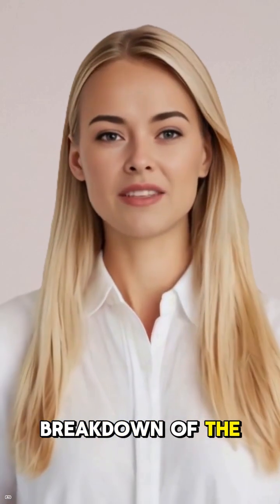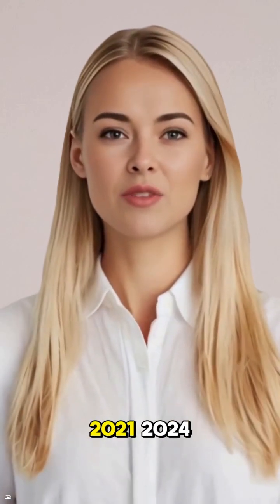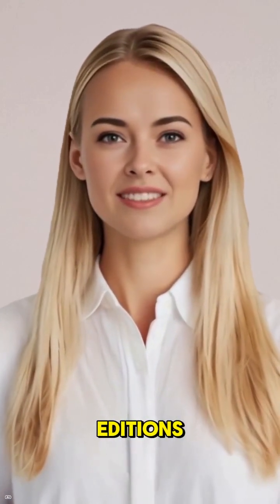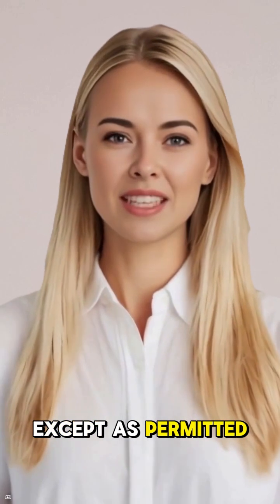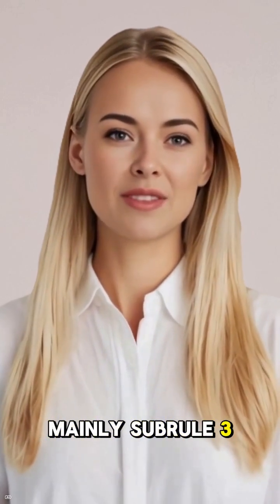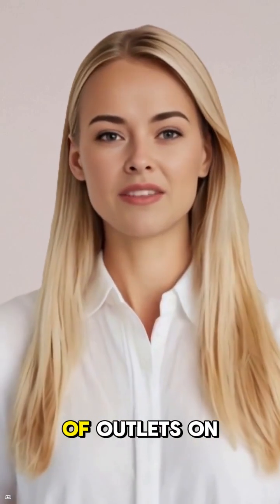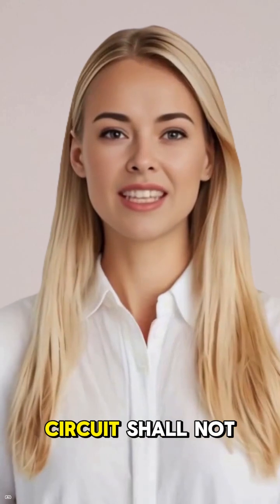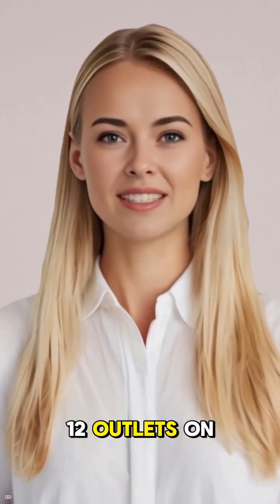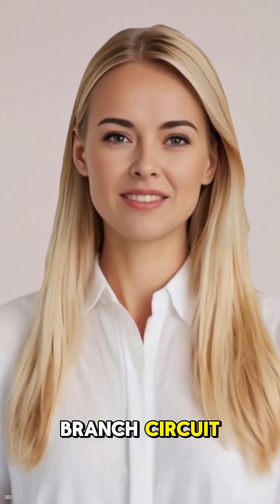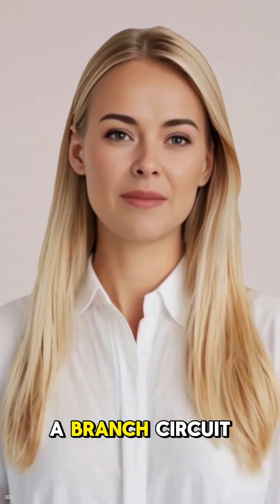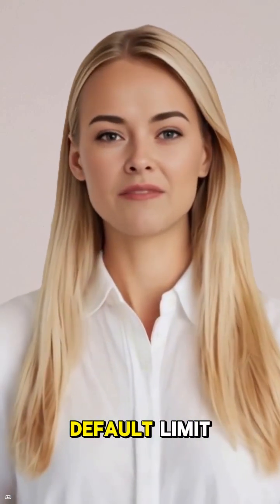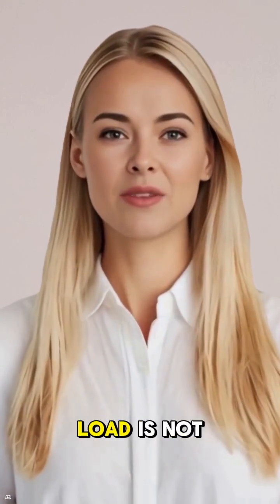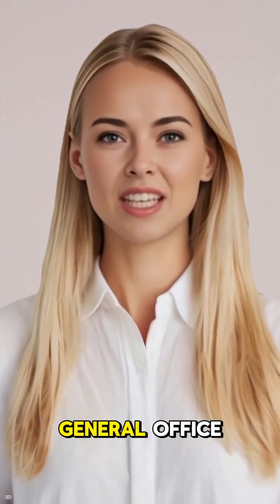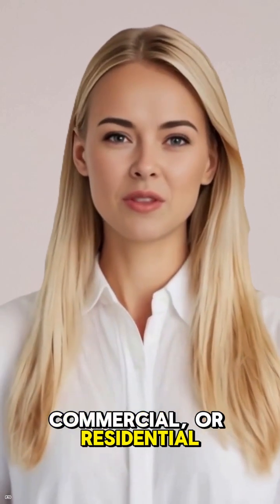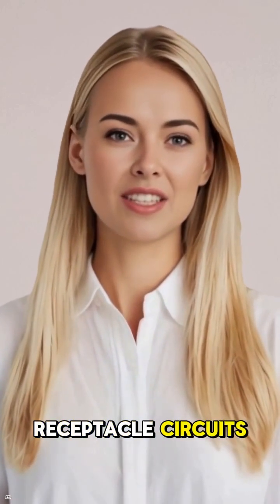Here is a breakdown of the main subrules based on the 2021-2024 editions. Subrule 1, except as permitted by other subrules, mainly Subrule 3: the maximum number of outlets on any 2-wire branch circuit shall not exceed 12 outlets on a 15A branch circuit, 16 outlets on a 20A branch circuit. This is the default limit when the actual connected load is not known, the most common case for general office, commercial, or residential general-purpose receptacle circuits.